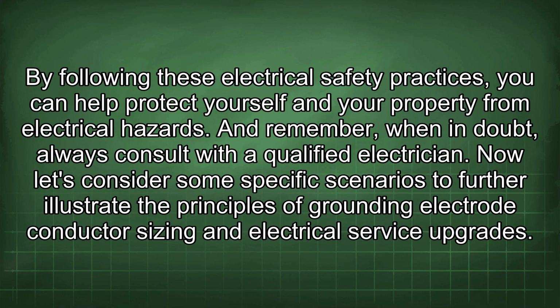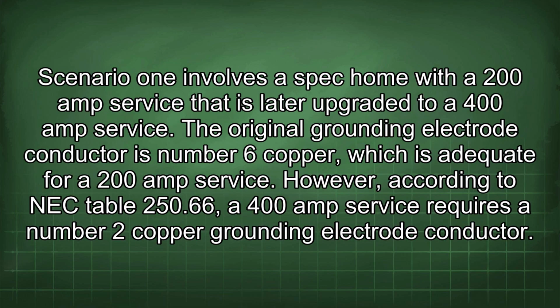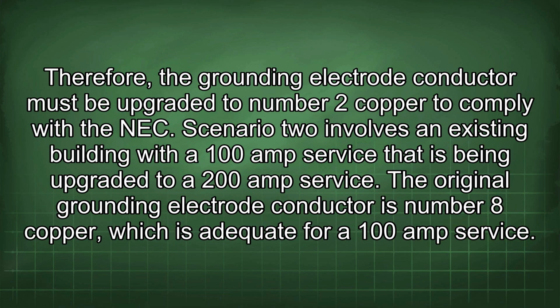Now let's consider some specific scenarios to further illustrate the principles of grounding electrode conductor sizing and electrical service upgrades. Scenario 1 involves a spec home with a 200 amp service that is later upgraded to a 400 amp service. The original grounding electrode conductor is number 6 copper, which is adequate for a 200 amp service. However, according to NEC table 250.66, a 400 amp service requires a number 2 copper grounding electrode conductor. Therefore, the grounding electrode conductor must be upgraded to number 2 copper to comply with the NEC.